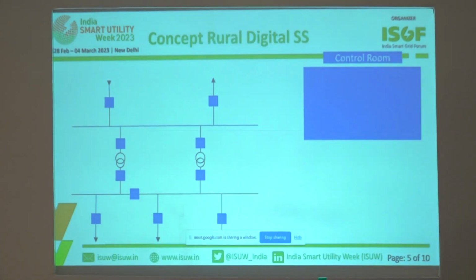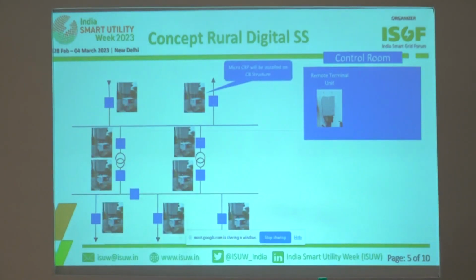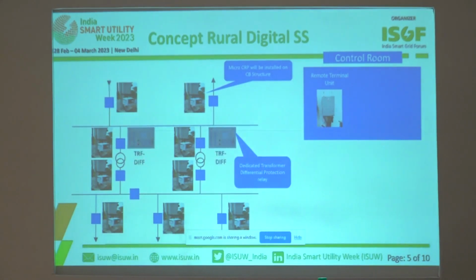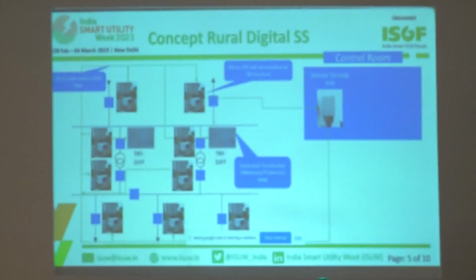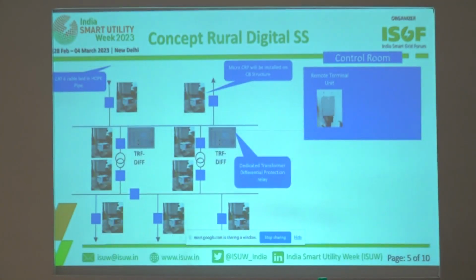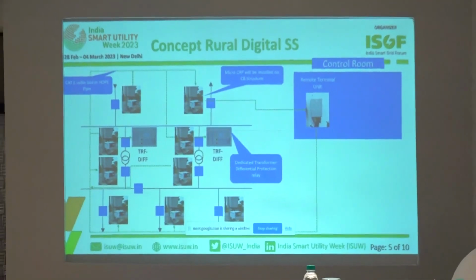So the concept of rural digital substation came after the brainstorming session we conducted within our teams. What we have done is place the remote terminal unit only in the control room along with the ACDB, DCDB. After that, all the micro CRPs - we have converted the big CRP panel into micro CRP. These CRP panels are placed on the breaker structure or an outdoor CT structure. From there, for transformer protection, we have again put the transformer differential relays in panels below the transformer, around the transformer area. All the cables required for communication establishment as well as AC and DC connections, we have laid through HDPE pipe.